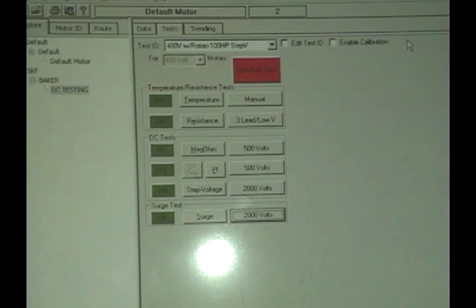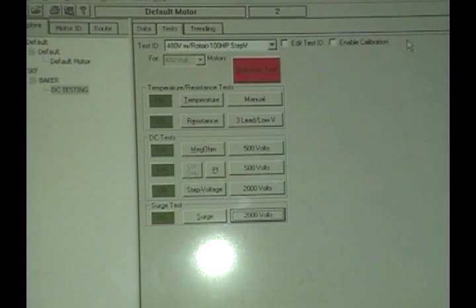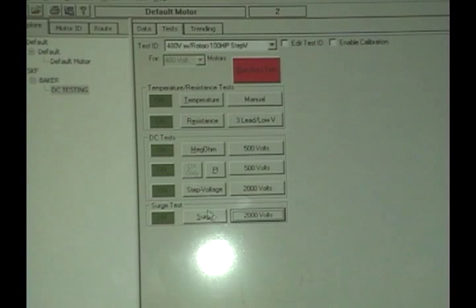When performing DC testing of armatures, we need to go into the surge screen and perform these tests manually. The way we do this is we move down to the surge button here.